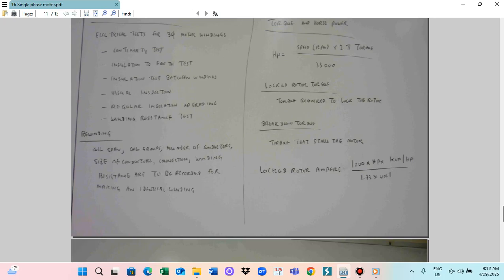This gap, and then the windings will be touching. The winding is normally enamel wire. Enamel wire is enamel coated, meaning insulation coated. But it is not too good, because with the windings, this iron body and this insulation cutting, it can cause an earth fault. An earth fault is too dangerous. Some operators can die because of an earth fault.